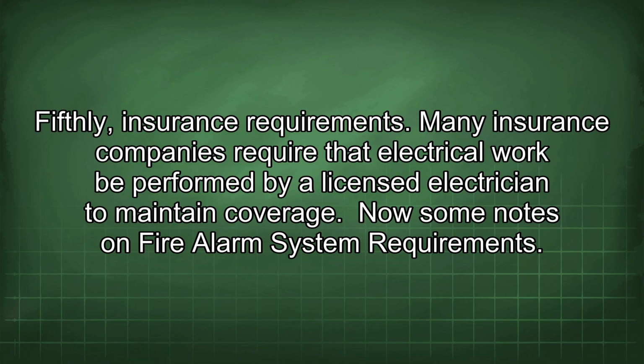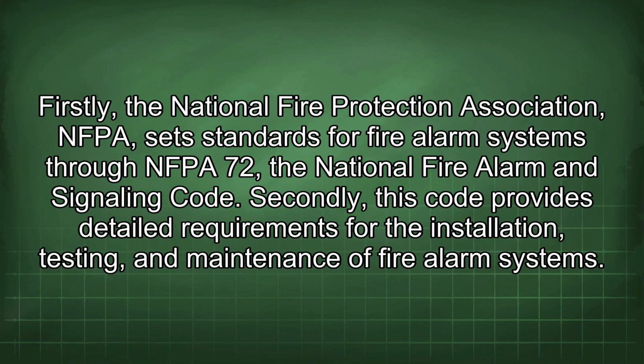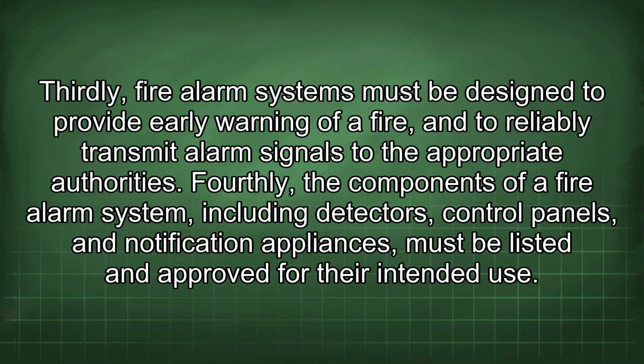Now some notes on fire alarm system requirements. Firstly, the National Fire Protection Association, NFPA, sets standards for fire alarm systems through NFPA 72, the National Fire Alarm and Signaling Code. Secondly, this code provides detailed requirements for the installation, testing, and maintenance of fire alarm systems. Thirdly, fire alarm systems must be designed to provide early warning of a fire, and to reliably transmit alarm signals to the appropriate authorities. Fourthly, the components of a fire alarm system, including detectors, control panels, and notification appliances, must be listed and approved for their intended use.